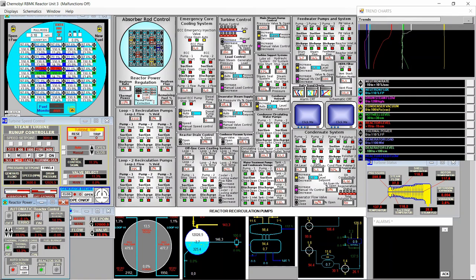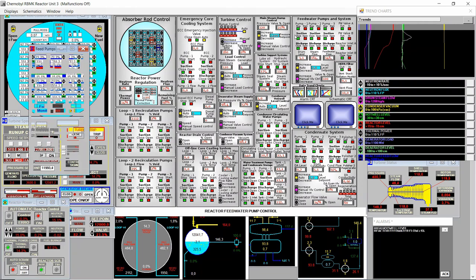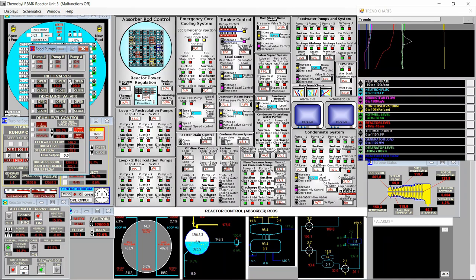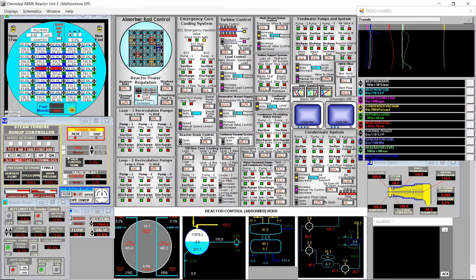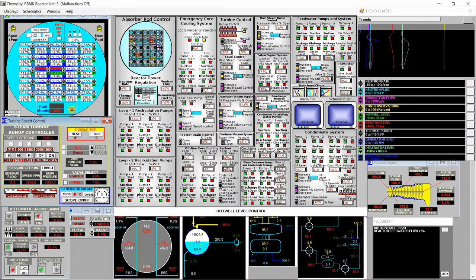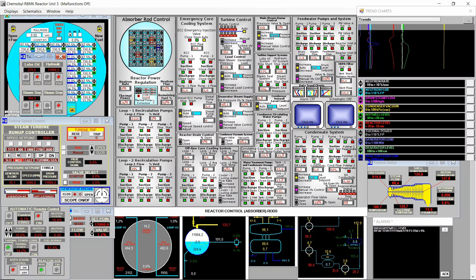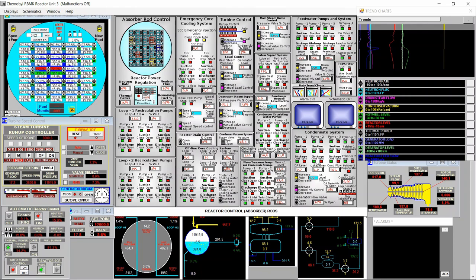To go further we need to connect the three feed water pumps: open the inlet valves, turn them on, and open the discharge valves. I connect the three-element control and main valve. The turbine control should be put into main valve, and the turbine support needs to close drains. Now we can keep increasing power.